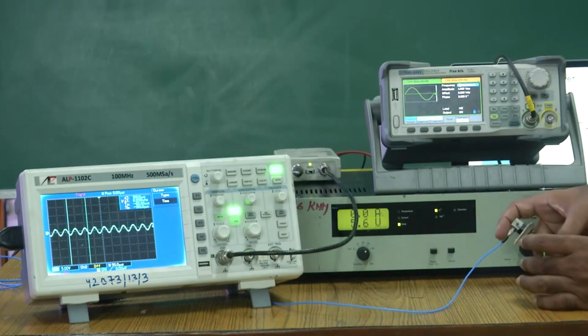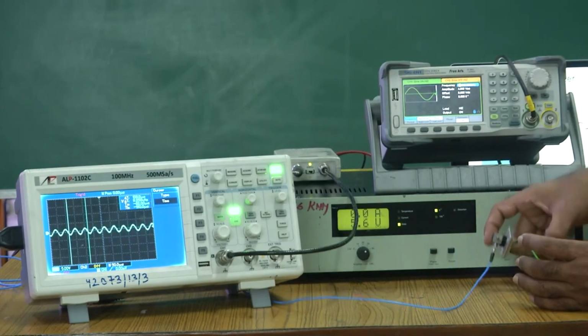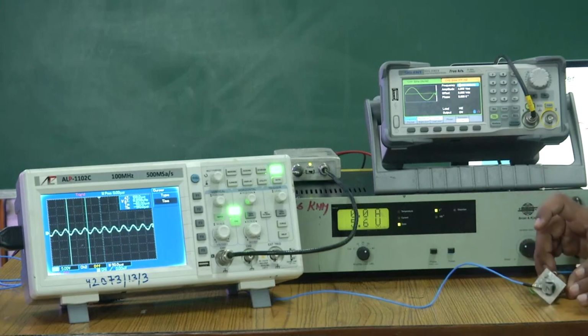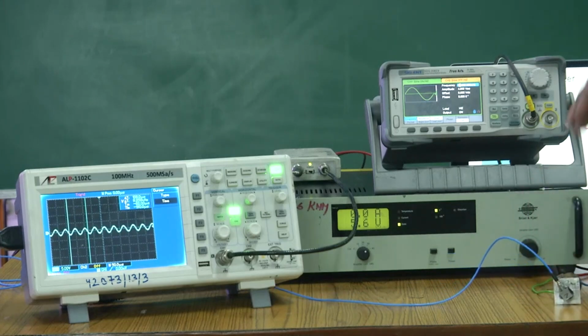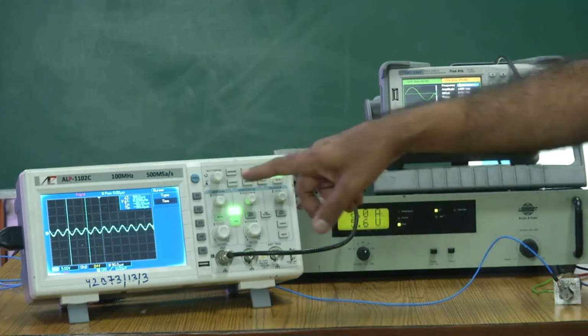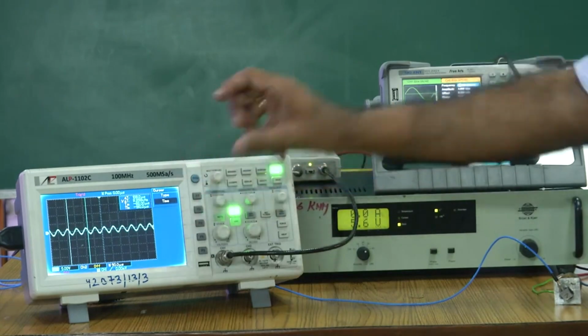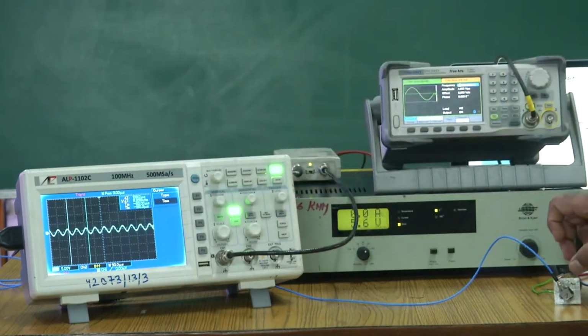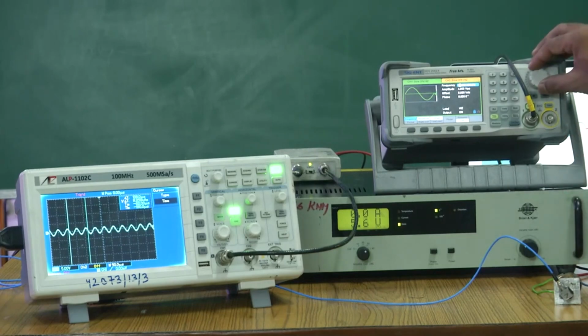Now the approximate natural frequency of this entire stack as a vibratory system is known. So I am going to scan through a small frequency range, starting with 18 kilohertz, and you can notice the amplitude will increase as I approach the natural frequency of this piezo stack sensor.